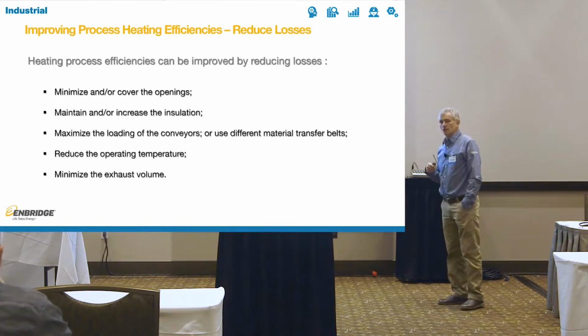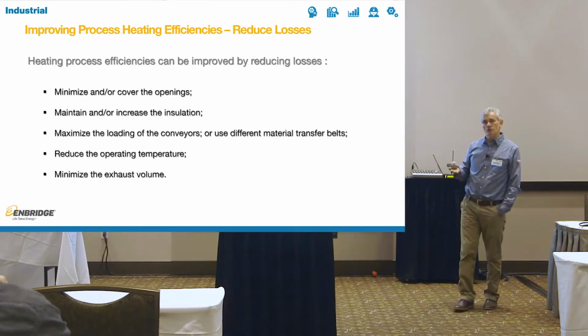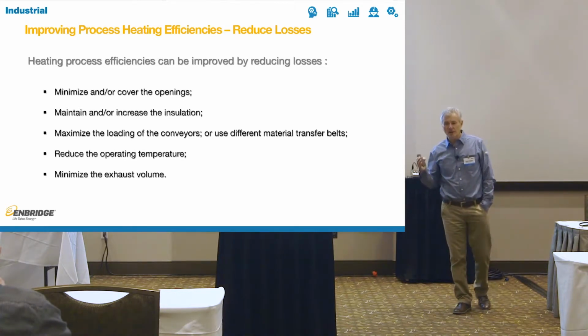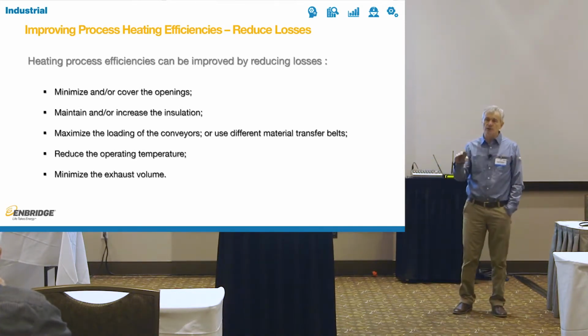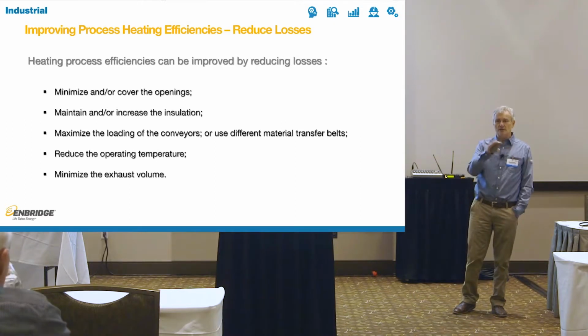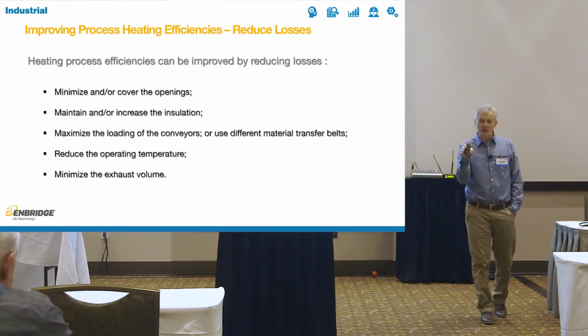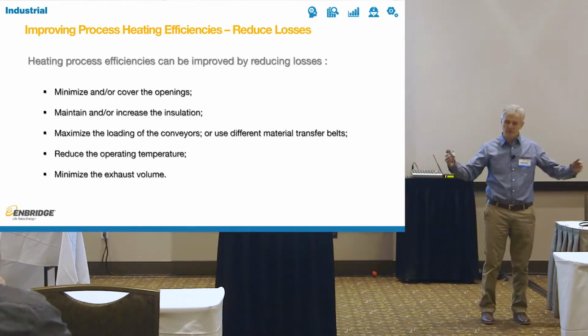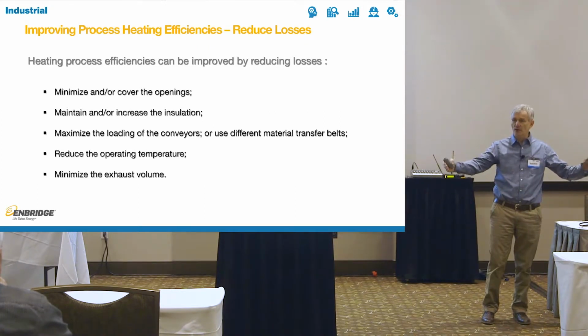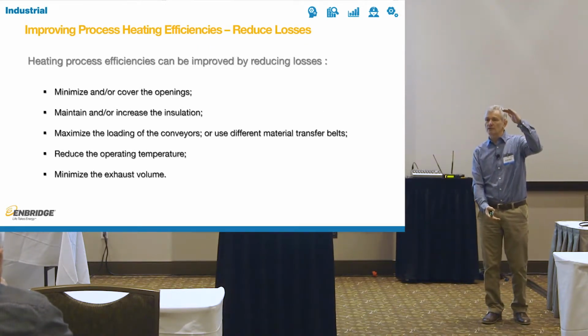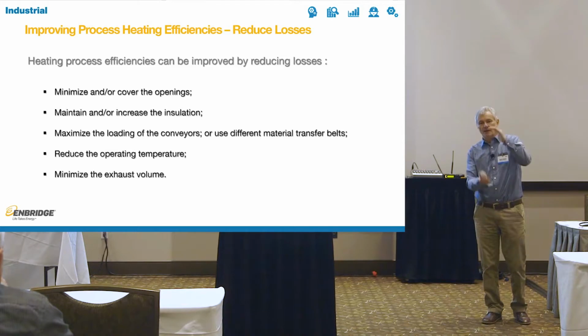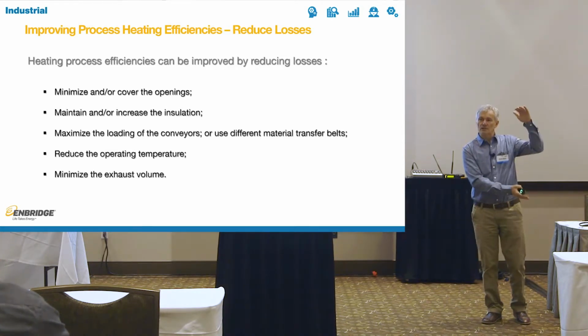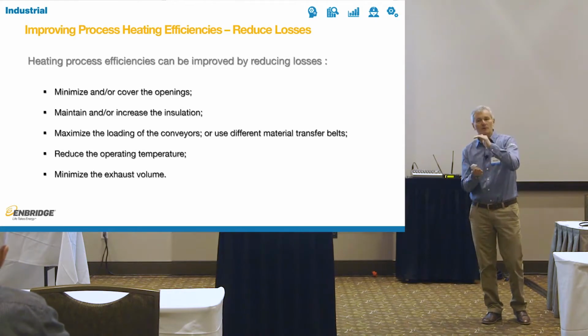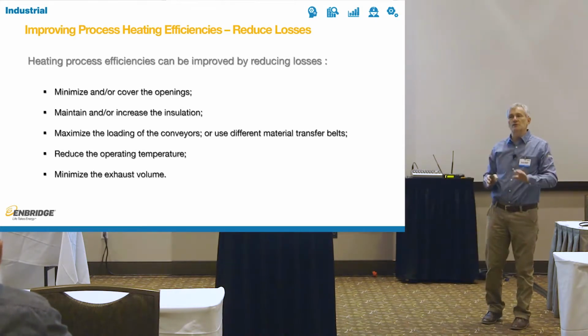So if we minimize or cover our openings, we're going to reduce the losses. Many people, especially on the finishing lines, have changed the size of what they run. I've seen many people who have, say, 3-foot wide by 8-foot tall openings into the oven, and they have parts this size going in, because way back when, the oven was designed for bigger parts. Now they operate with smaller parts. Well, close off those openings if you can.